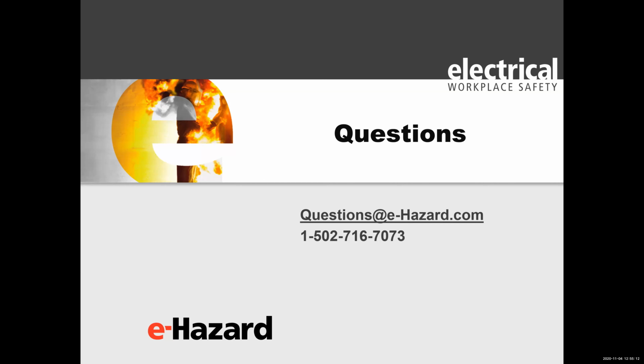Next question we have is, are arc flash warning labels required on all electrical panels, and are older buildings required to update that labeling where they do not exist? Well, since 2005, it's been required in the National Electric Code. So that's law in most states. The grandfathering idea, if you've never changed anything, could perhaps apply. I'm not a legal expert. I would always recommend you start the process. The general warning labels of arc flash and shock hazard are not really very useful, but it's better than nothing.